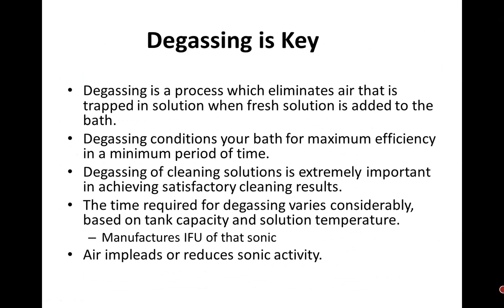Degassing. Degassing is key. As I said, many of the new models already have that built in: it fills the tank, degasses even though you put the instruments in there, then runs the cycle. They've gone through a validation process of that. Degassing is something where there is trapped air in solution, and this we have to accept. There are physicists and chemists you can read on this: when you have a new tank or you put water in, there is trapped air. The degassing is releasing that air because air impedes cavitation. Just like a sterilizer, if there's trapped air in your sterilizer, the sterilization process won't work. That's the analogy I try to use. So you are degassing and freeing up that air so you can get maximum efficiency in the time that you are going to use it.